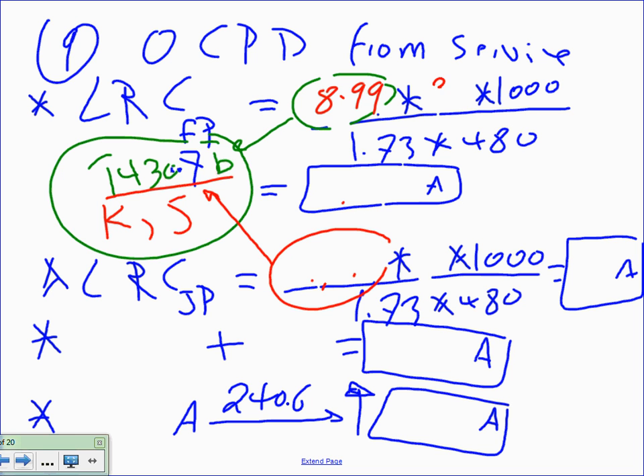Multiply this by 30 because we have 30 horsepower for that fire pump. And that will give you 324 amps. Same thing for the jockey pump, except the jockey pump is going to be 7.99, if I did that right. And you multiply it by 7.5 and divide by the same voltage because they are the same, so they'll give you 72 amps for this baby.